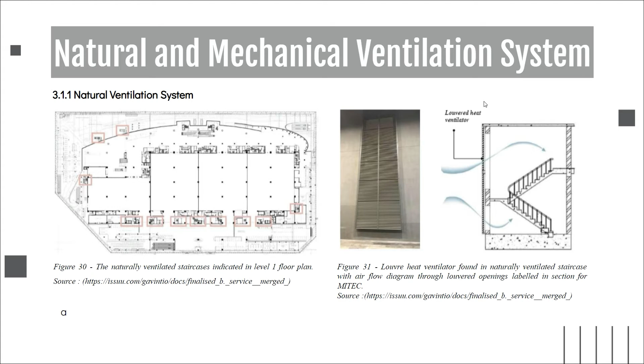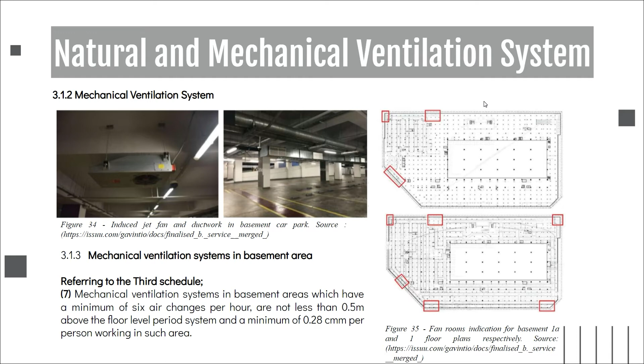Referring to the third schedule, we need to have a minimum of 6 air changes per hour for the mechanical ventilation system in basement areas, at points not less than 0.5 meter above the floor level, and a minimum of 0.28 cubic meter per minute per person working in such areas. They use exhaust ventilation, and this operation is used in the car park basement. It performs by depressurizing the building, which is exhausting air from the structure, causing a change in pressure and pulling in makeup air from outside through leaks in the building shell.